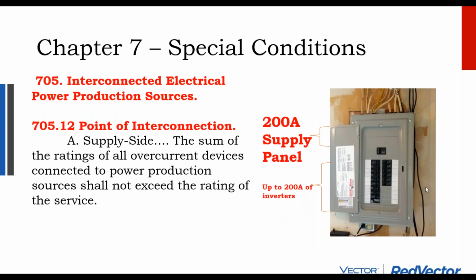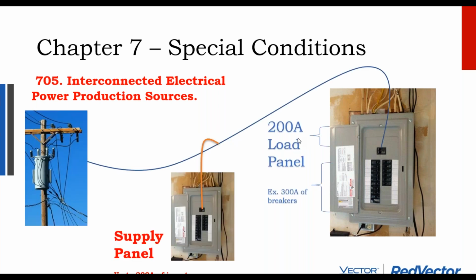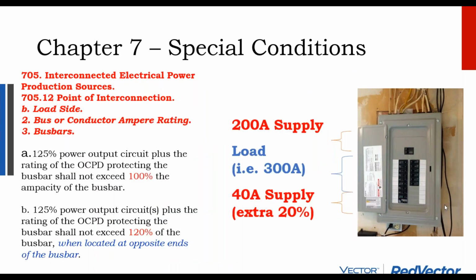In terms of sizing the electric service, long story short, you got two areas where you can connect to: the supply side of the panel or the load side of the panel. And so the supply side is between the utility transformer and the top of your breaker, whereas the load side of the panel is connecting where all of your other breakers are. And we don't have time to get into too many details on this, but essentially, if you count up all the breakers on your electric service panel, it might be a 200 amp panel, but you count up all the breakers, it's 300 amps. You're like, well, how is this not catching on fire?